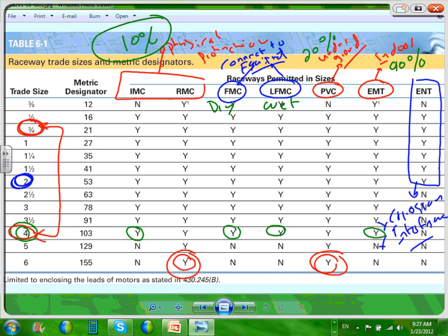Because I was so lazy, I don't like building conduits and I'm not good at it. So right here in Minneapolis I wired a couple of fixtures and lights in the basement with flexible metallic conduit. Can I do that? Yeah, no problem. The problem is pushing the conductor through that baby is a nightmare. It's not worth it. You have to put your fish tape in there, and God forbid you use a metallic fish tape in that one, it wouldn't move. So you have to use non-metallic fish tape, and then pull all these conductors. It's a real nightmare in distances longer than, I would say, 10 feet.